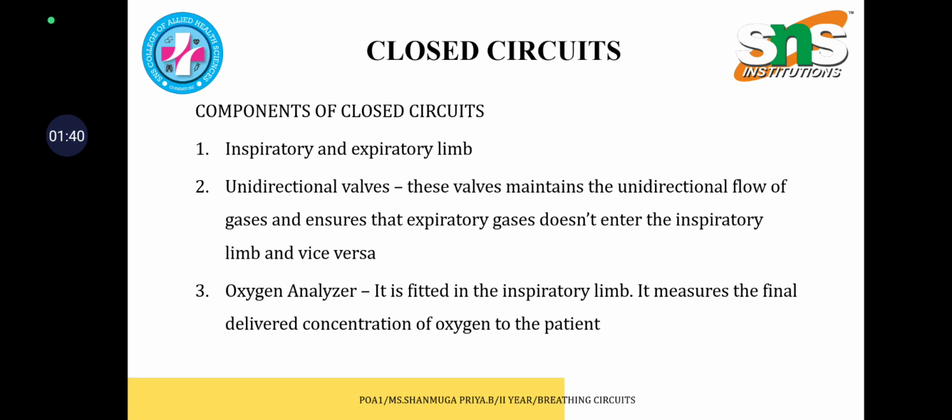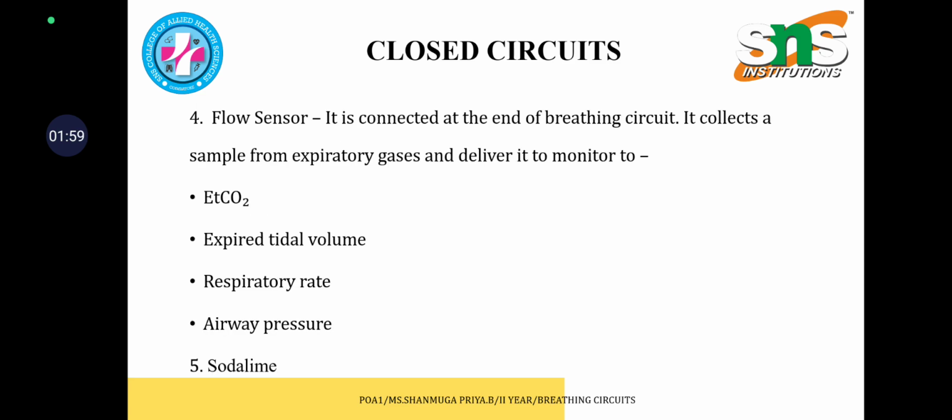These valves maintain the unidirectional flow of gases and ensure the expiratory gases do not enter the inspiratory limb and vice versa. Oxygen analyzer, it is fitted in the inspiratory limb. It measures the final delivered concentration of oxygen to the patient. Flow sensor, it is connected at the end of the breathing circuit.